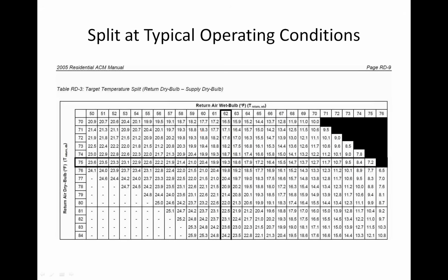And you can see here, well, I don't know why I blocked this section out. I have to go back and look at my notes here, or why I had this 19.3 degrees here at 62-degree wet bulb. Oh, this is corresponding to 50% relative humidity at 75 degrees indoor air temperature. So under normal conditions, if the return air dry bulb is 75 and humidity is 50%, this is where that 20-degree drop across the coil came from.